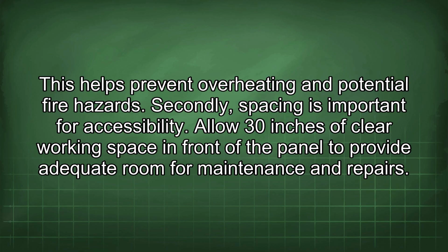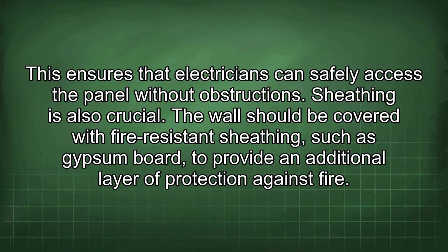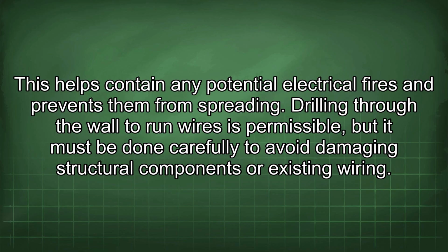Secondly, spacing is important for accessibility. Allow 30 inches of clear working space in front of the panel to provide adequate room for maintenance and repairs. This ensures that electricians can safely access the panel without obstructions. Sheathing is also crucial. A wall should be covered with fire-resistant sheathing such as gypsum board to provide an additional layer of protection against fire. This helps contain any potential electrical fires and prevents them from spreading.